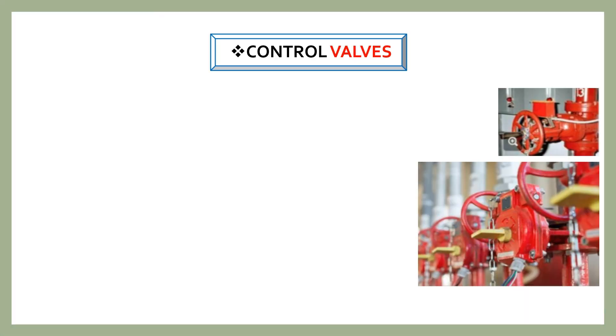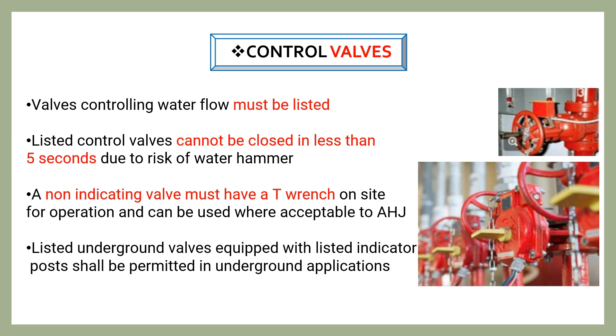Control valves can be gate valves or butterfly valves. Valves controlling water flow must be listed, and listed control valves cannot be closed in less than 5 seconds due to the risk of water hammer. A non-indicating valve must have a T-wrench on site for operation and can be used where acceptable to the AHJ. A non-indicating valve will be installed underground, and listed underground valves equipped with listed indicator posts shall be permitted in underground applications.